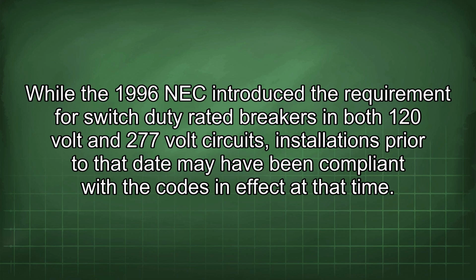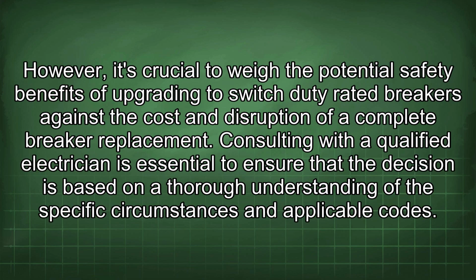While the 1996 NEC introduced the requirement for switch-duty rated breakers in both 120-volt and 277-volt circuits, installations prior to the date may have been compliant with the codes in effect at the time. However, it's crucial to weigh the potential safety benefits of upgrading to switch-duty rated breakers against the cost and disruption of a complete breaker replacement. Consulting with a qualified electrician is essential to ensure that the decision is based on a thorough understanding of the specific circumstances and applicable codes.